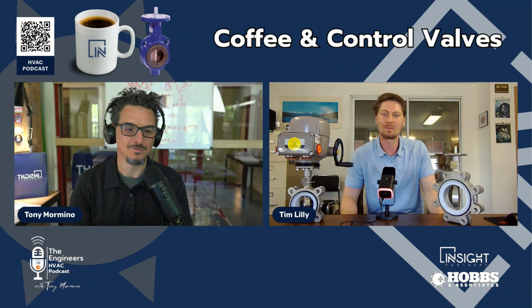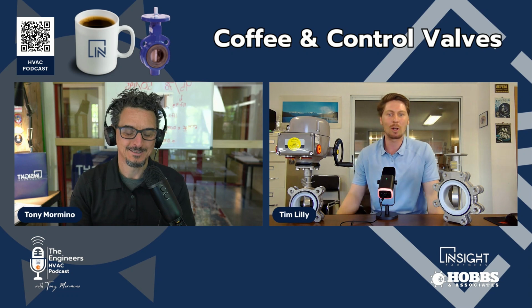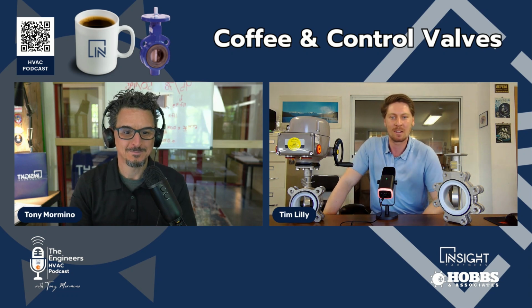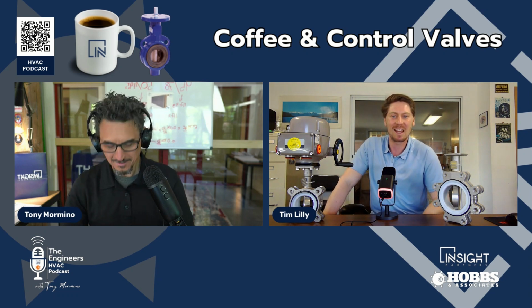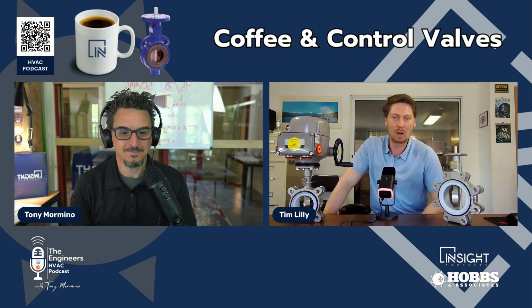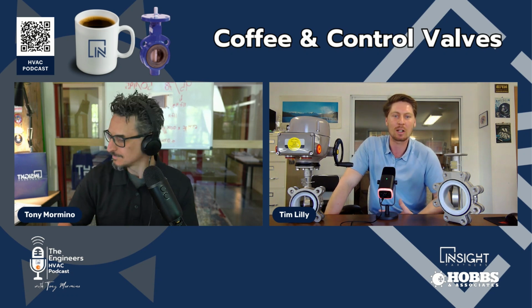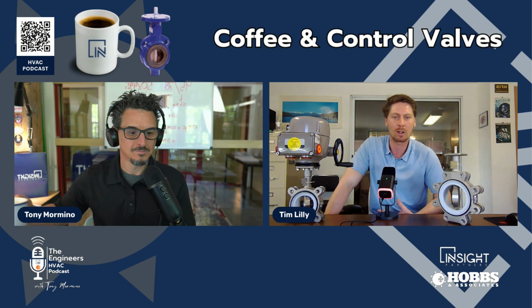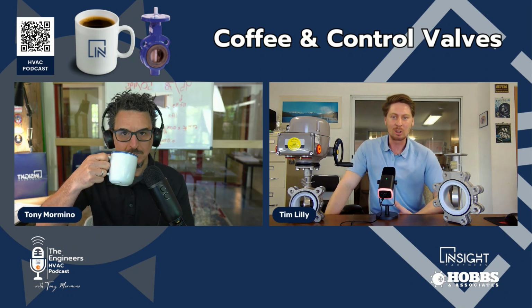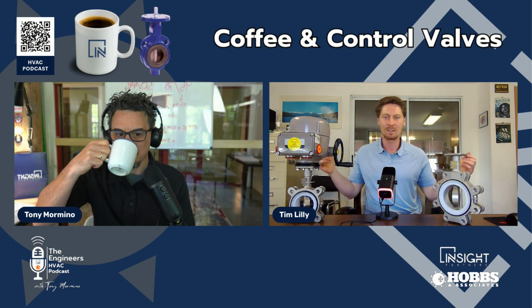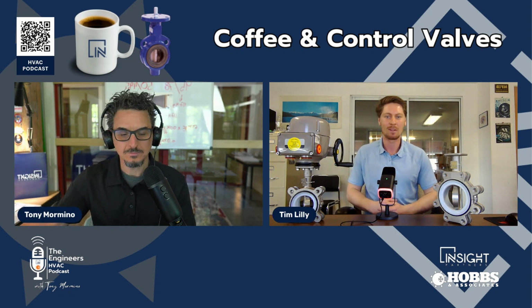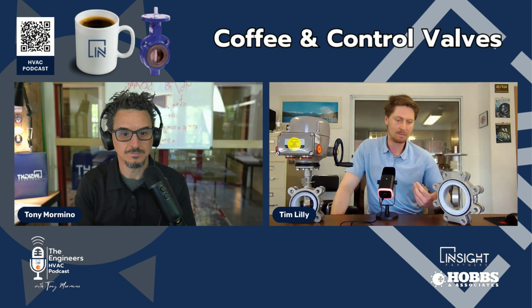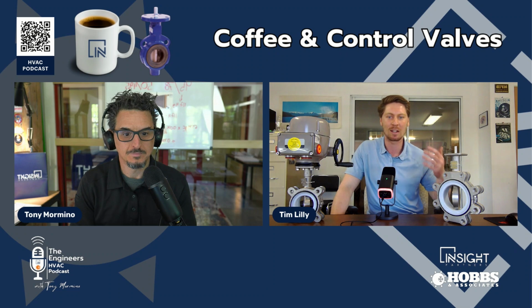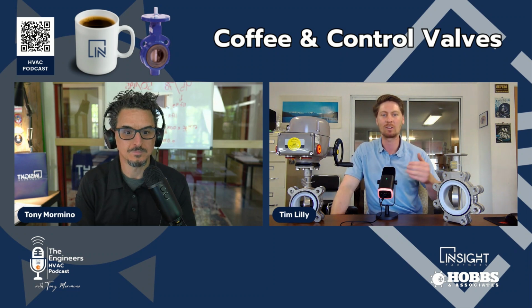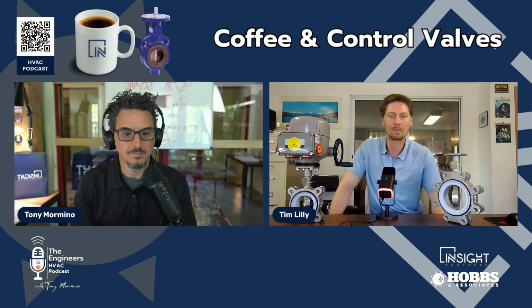I'm just like general valve sizing 101, trying to get my head around that. Yes. So valve sizing, you do it based on what's called CV. I was hoping you'd bring up CV. And it's a coefficient. What it does is it takes into account your pressure, your flow, your temperature, and your liquid. So it's basically just a way to put everything on the exact same playing field. That way you can size for every single application, and it's a standardized unit is what it is.